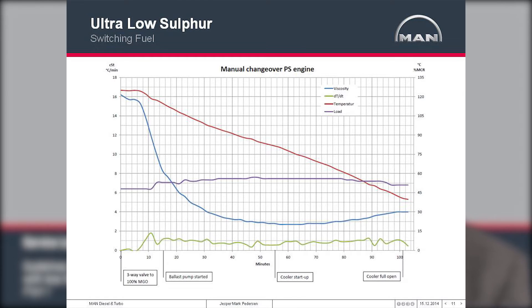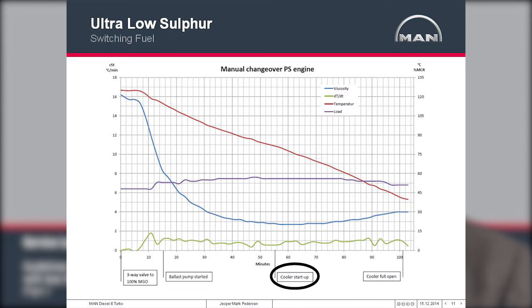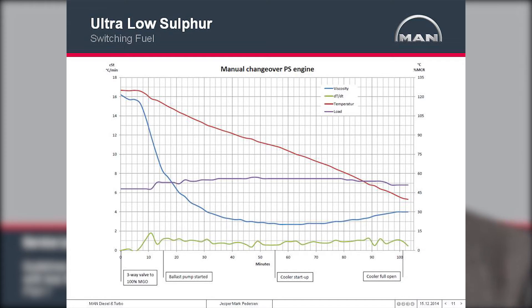Halfway through the changeover, the coolers for the fuel system had to be engaged to keep the viscosity high enough to avoid seizures in the fuel pumps. Looking at this example, the changeover should probably have been done at a lower engine load.